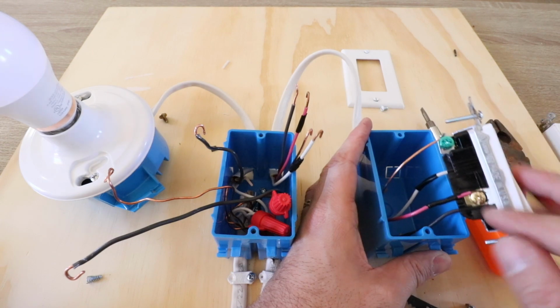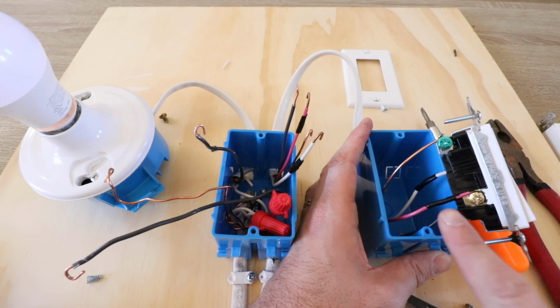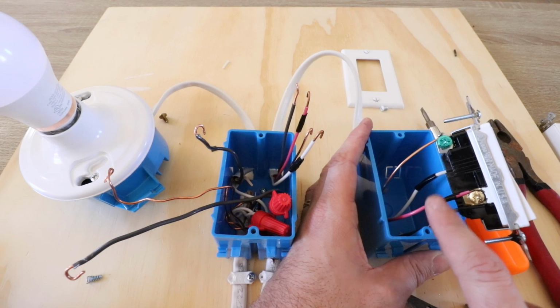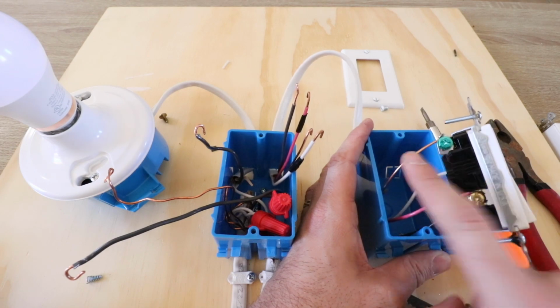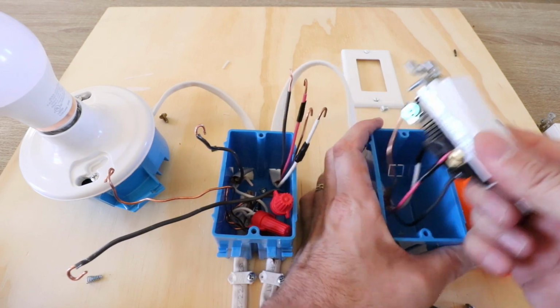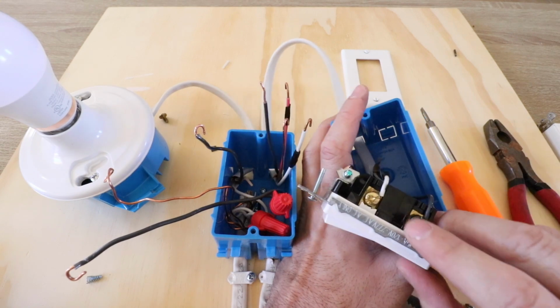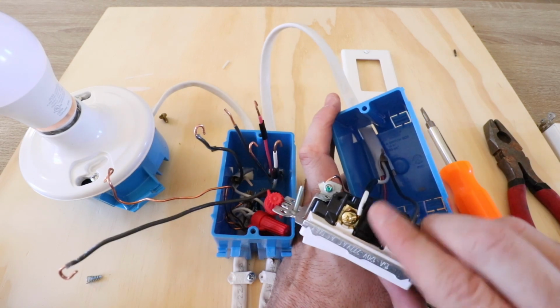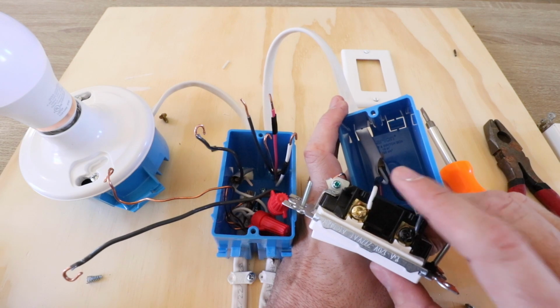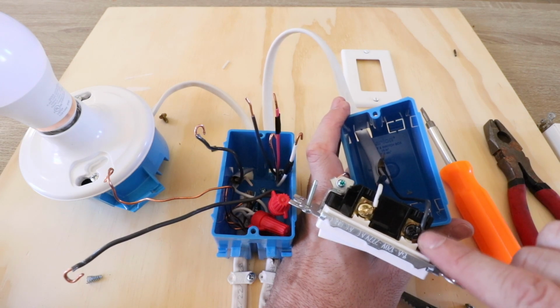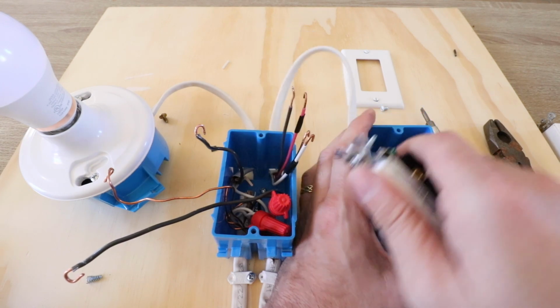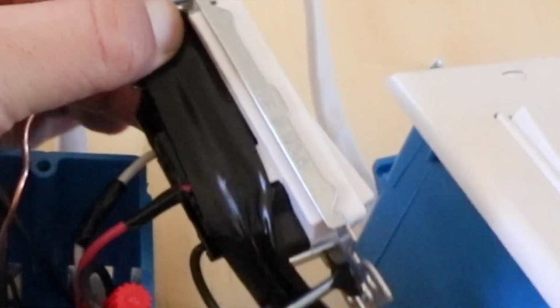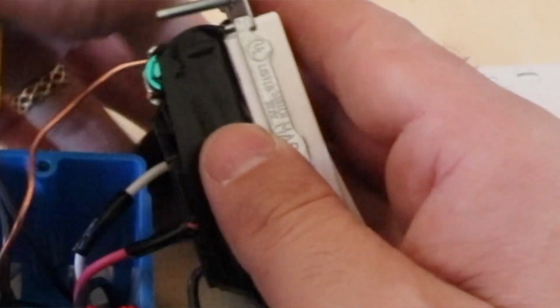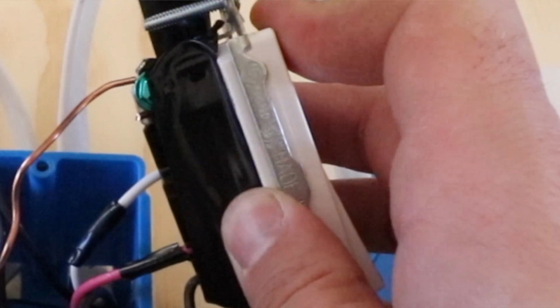All right, we have all the wires wired up here. We've got our traveler wire on this side, and our ground wire here wired up as well. On the other side of the switch, we wired up our traveler at the top, designated with that tape marking, and we've got our line switched, or hot switched, wire here. Now it's always a good idea to take some electrical tape and cover up the terminals on the switch to prevent the possibility of them touching another wire and shorting out.